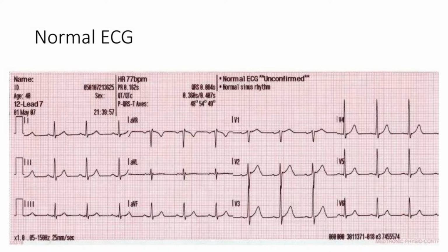So this is how a normal ECG would look. I projected this slide to emphasize the little settings or writings that we will often ignore. We already spoke about the amplitude, which is usually done at 10 millimeters per millivolt. Usually at the very far left of the ECG, you'll find this marker that will usually cover two big boxes to suggest that it was done at 10 millimeters per millivolt. Then look at your speed to ensure that it was done at 25 millimeters per second.